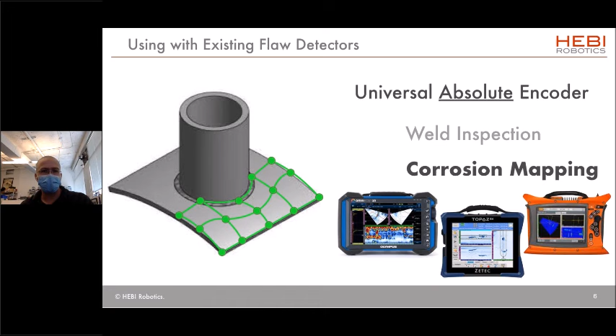The second application we'll show is also corrosion mapping. The weld inspection is sort of a one-dimensional case. In a two-dimensional case, you can lay out a grid of points. Again, this can be loosely done by hand, because what the software does is then connect these points with a set of smooth curves. Similarly to how we can unwrap a single line, we can now unwrap an entire map, as if you're putting a map on the surface of the earth, right? You can stretch that out and wrap it.